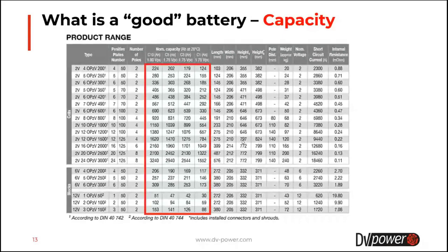If we have a more powerful device for battery testing, we can perform a C5 rating test, and the current in that case would be 202 divided by 5, and we will perform a 5-hour test with a discharge current of 40.4 amps. 202 amp hours is the C5 rating capacity of the same battery. The capacity for the C5 rating test is smaller than the C10 rating capacity because we use a higher current to perform the test, and the voltage drop as well as heating of the battery is greater because of that higher power.